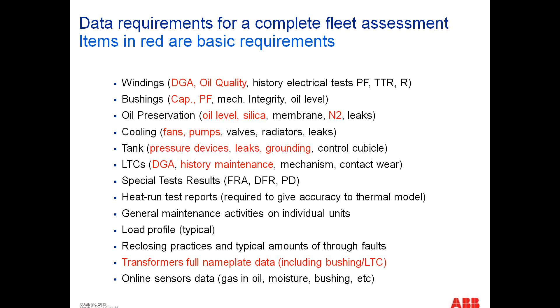Risk of failure is one item, but the importance of the transformer is another key aspect you have to look at. Just knowing your transformer is a little unreliable isn't enough. If you've got 3 or 4 ways around that transformer to deliver power to customers, that's not nearly as urgent as, say, a generator step-up transformer, where if you lose it, the power plant goes down. And as the tsunami unfortunately showed us, auxiliary transformers that run key systems in plants may be small, only 10, 20, 30 MVA, but they might be critical to the operation or even the safety of a nuclear power plant.